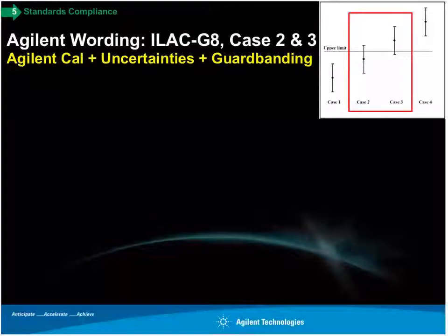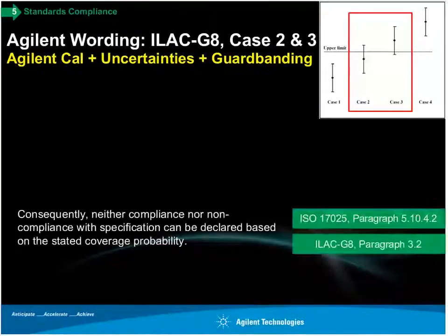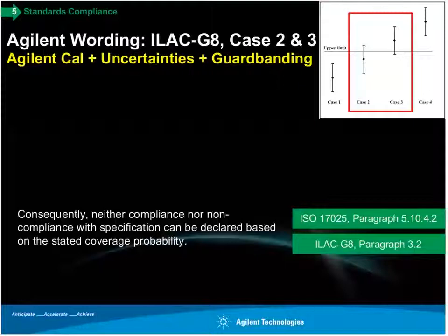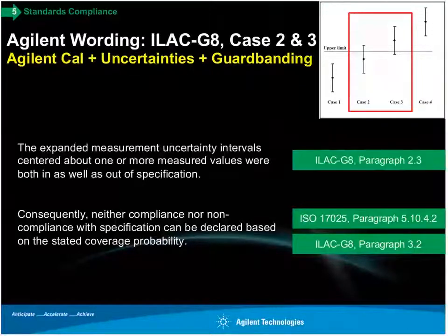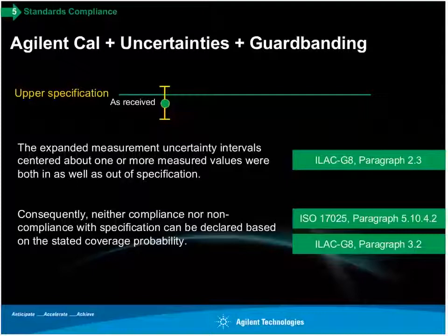And the answer is absolutely yes. We call that service Agilent Cal plus Uncertainties plus guard banding, and that's really either case 2 or case 3 that you see in the upper portion of the diagram there. Either one of those, we mark as undetermined as received. Now, of course, you don't want to receive the instrument back as undetermined.